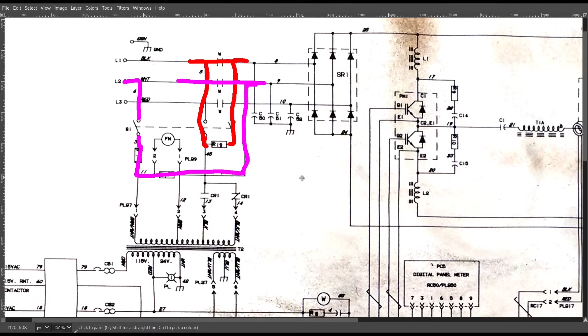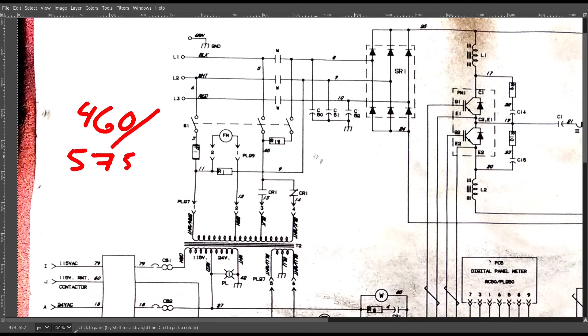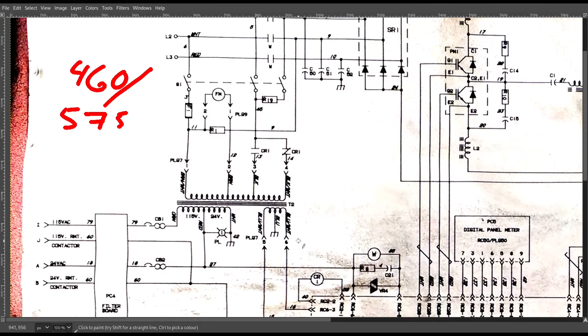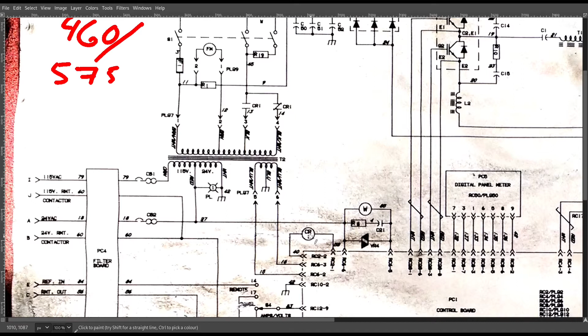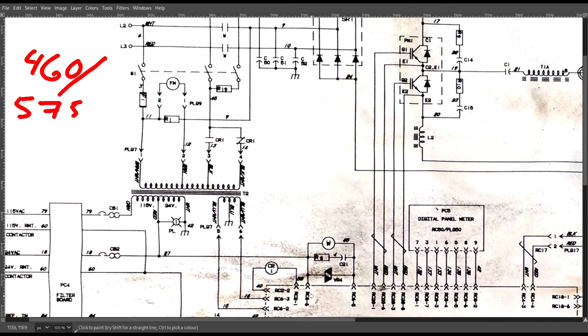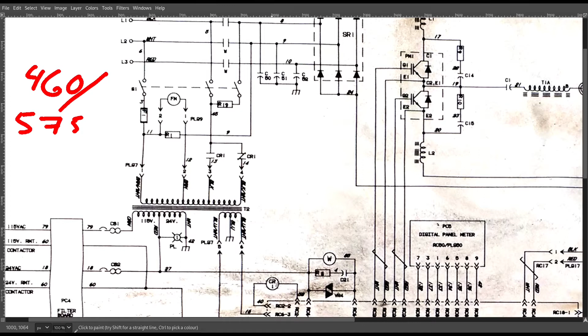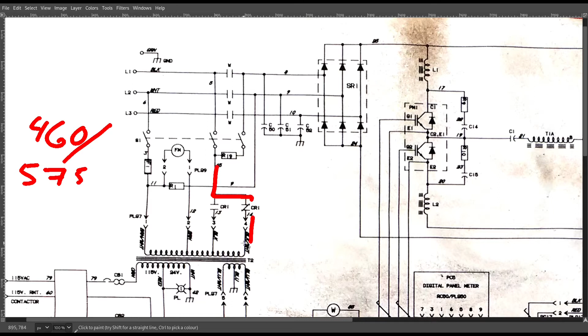Next, on my unit, on the 460/575 volt versions, the power sections are always stacked in series, as I was showing, but there's still an auto link relay. It's CR1, which is mounted close to the fan on mine. It's also controlled by the main PCB, and the way this works is from this winding here, which provides plus and minus 24 volts. If the control board detects that it's not 24, then it will energize CR1. So by default, when you power it on, to be safe, it assumes that you hooked up 575 volts to it, which means line 1, which feeds this control transformer, goes in here through the normally closed contact, and it energizes the longer winding.